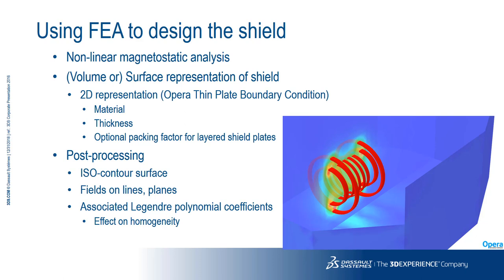When defining the shield in a finite element analysis system, you'd normally define a volume representing the three-dimensional limits of the individual plates of shield material. This can lead to numerical difficulties due to large aspect ratio elements if you don't use facilities such as Opera's mosaic meshing to introduce tetrahedral elements. Large aspect ratio tetrahedra can result in inaccurate answers or convergence problems. So in Opera we've additionally implemented the means to represent the shield material as purely a surface with a property giving the material and thickness, and users can make use of laminated materials. This thin plate boundary condition eliminates any issues around aspect ratios and numerical difficulties. MRI designers also need to view ISO surfaces, fields on planes, and calculate associated Legendre polynomial coefficients — we'll take a look now at how all of these are achieved in Opera.